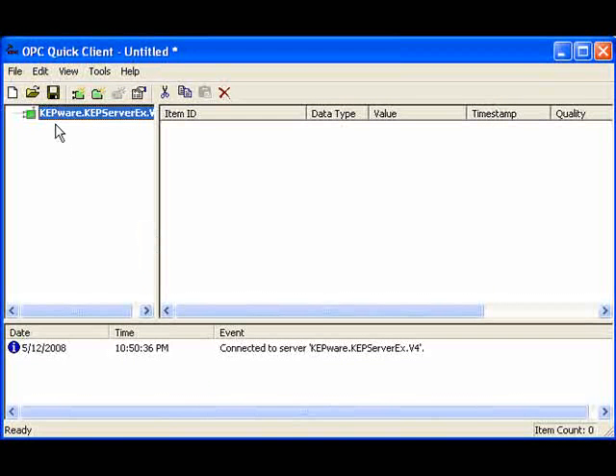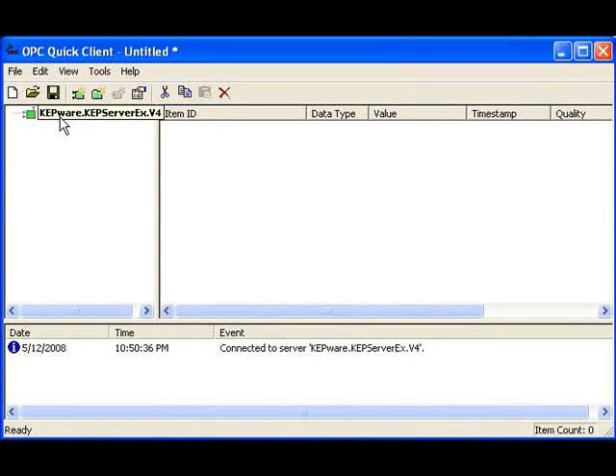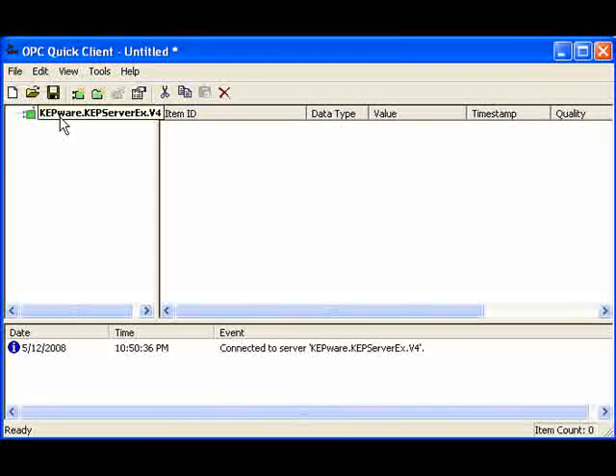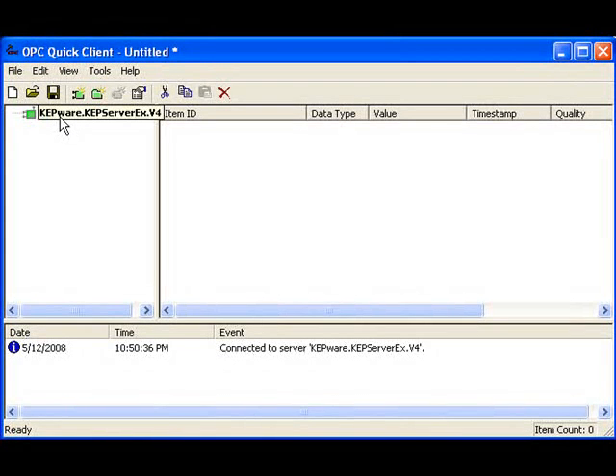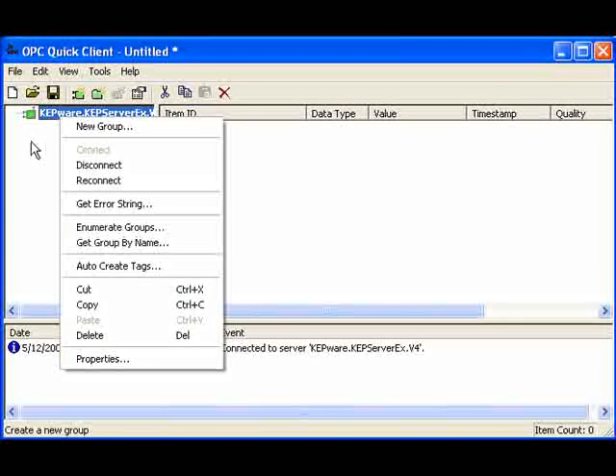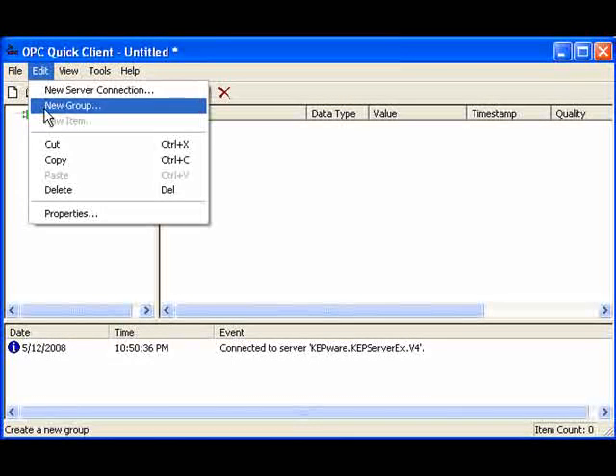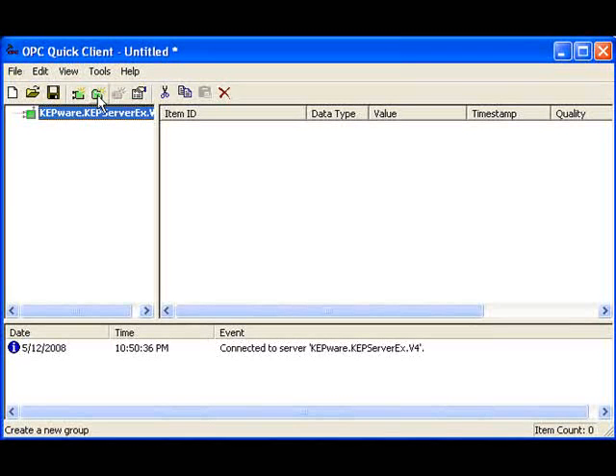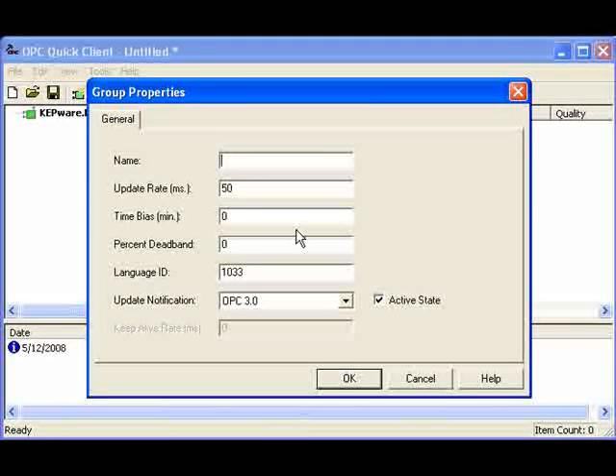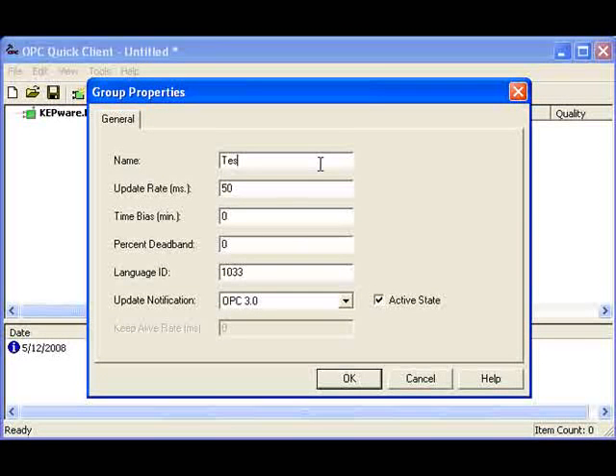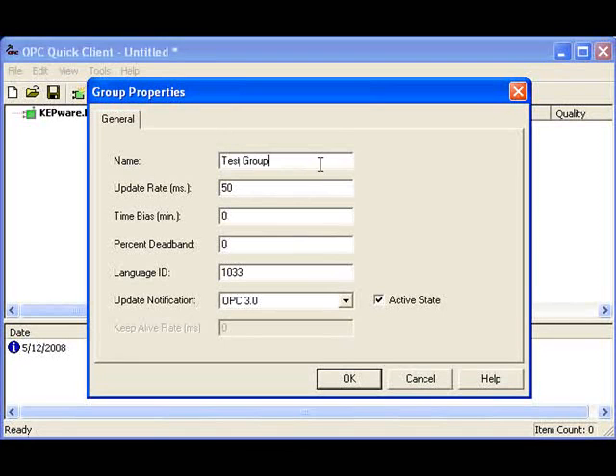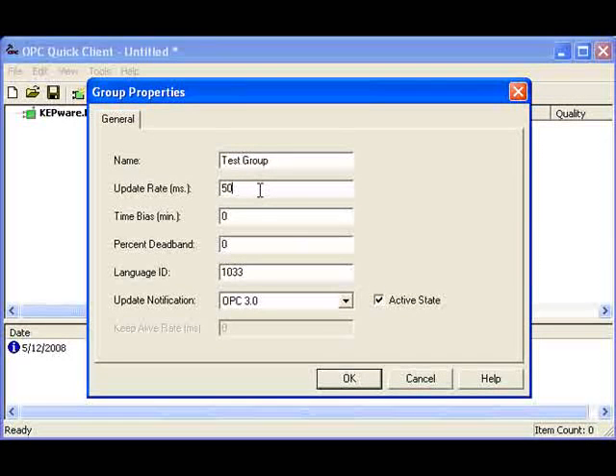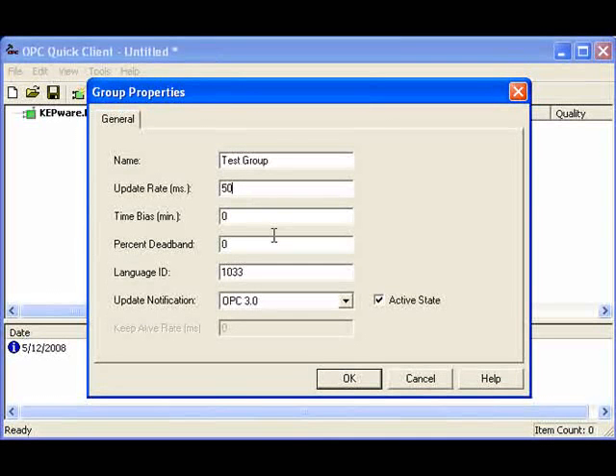The OPC Quick Client shows us that we have a connection to the OPC server. Next, we need to add a Group, which is what's required in OPC Data Access. To do that, we can right-click on the OPC server and hit New Group, or we can click on Edit New Group, or we can click on the New Group button right there, which is what I'll do. I'll call my group the Test Group and you can see that the update rate is already set to 50 milliseconds or 20 times per second. I'll click on OK.